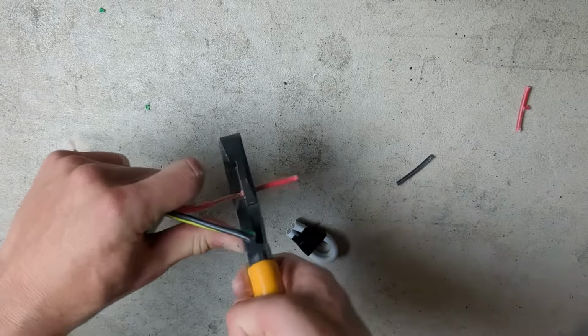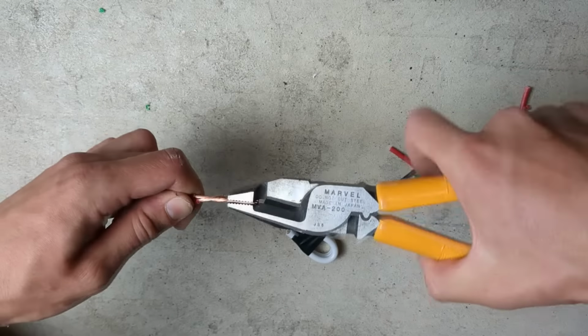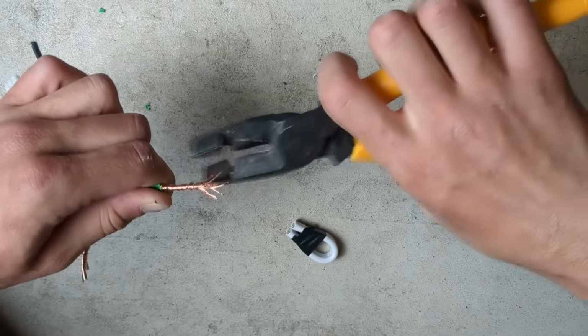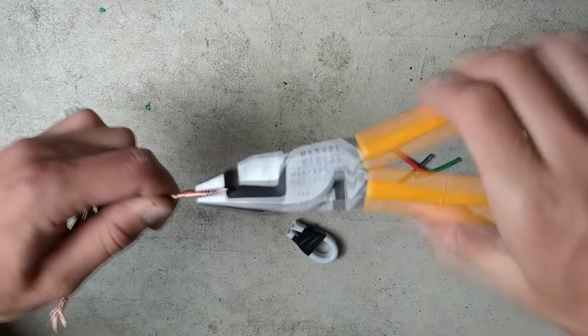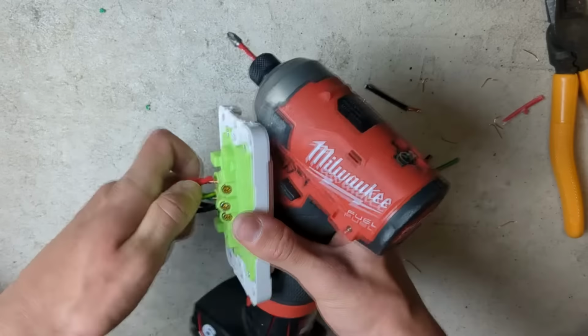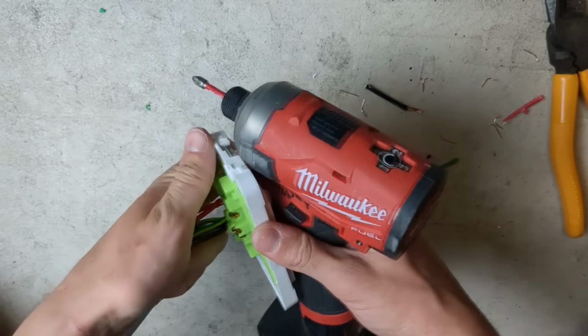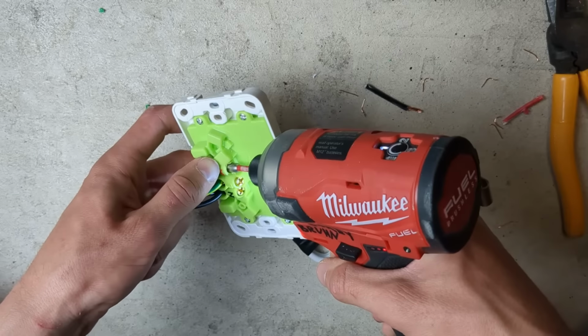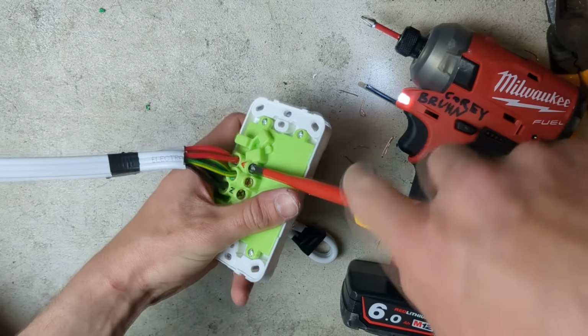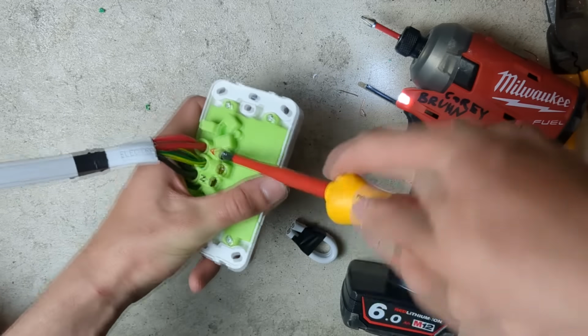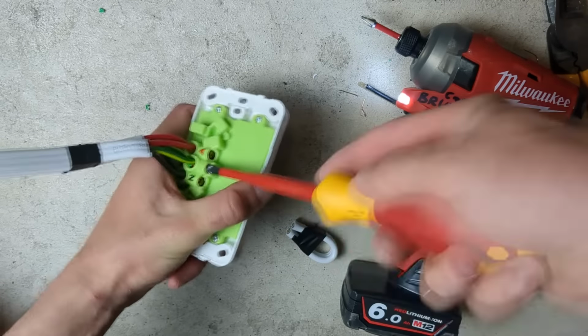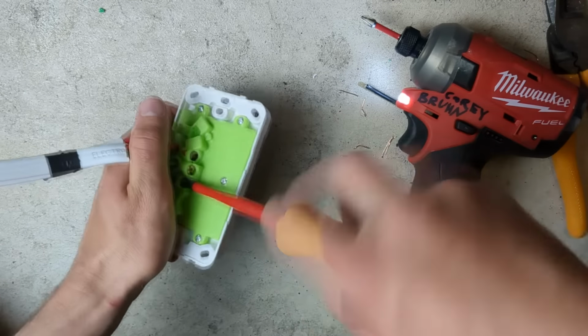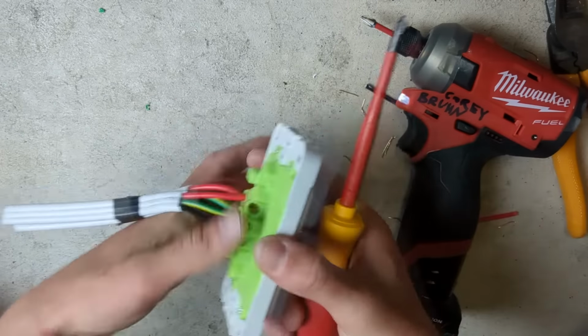When I'm fitting off a power point, I make sure I twist the strand of copper and fold it in half if it's a single end. If there's multiple ends, I'll twist the copper together, put them in the terminals, get my impact driver on the lowest setting, tighten that up, and finish it off manually with my screwdriver just so I know the screws in the terminals are tightened securely.